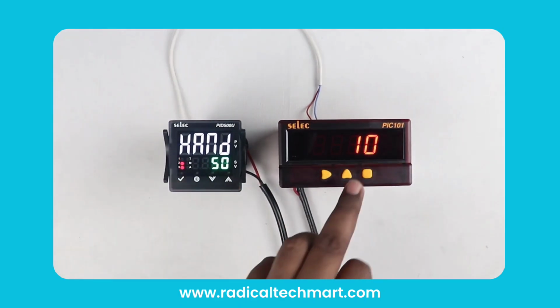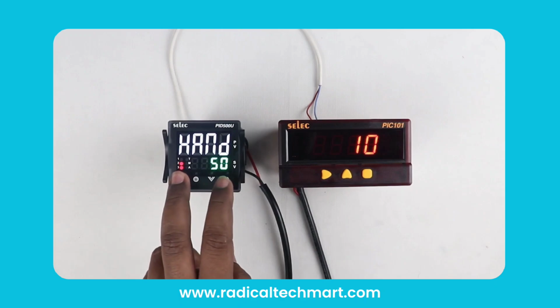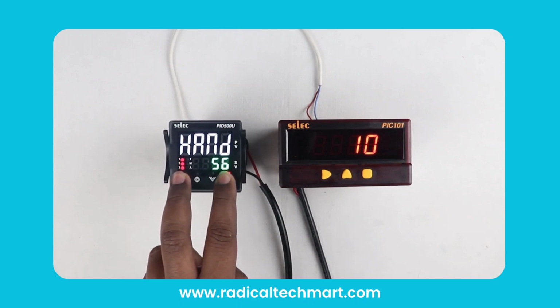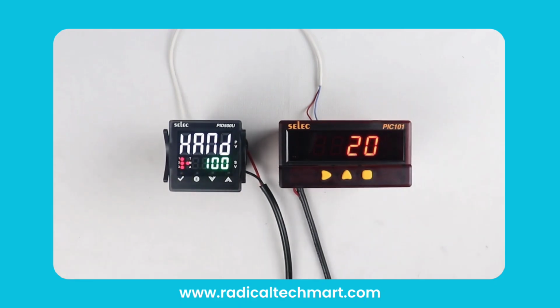In a demonstration, when a 50% output is given for a 4 to 20 milliampere input scaled to 0 to 20, the display shows 10. When the output is increased to 100%, the display shows 20, reflecting the maximum scaled value.